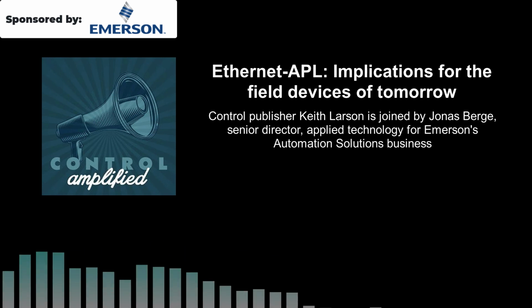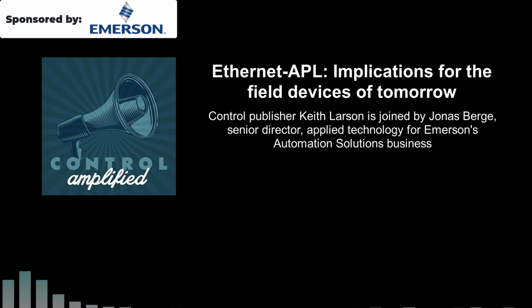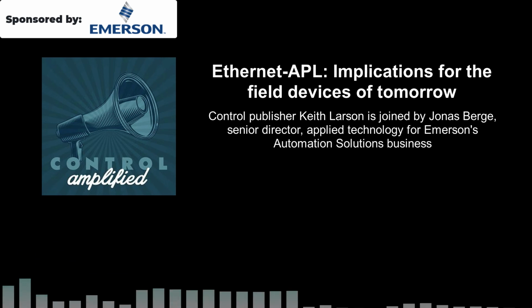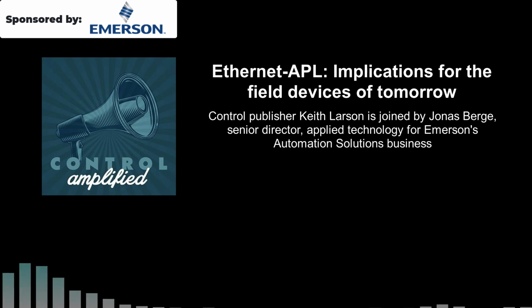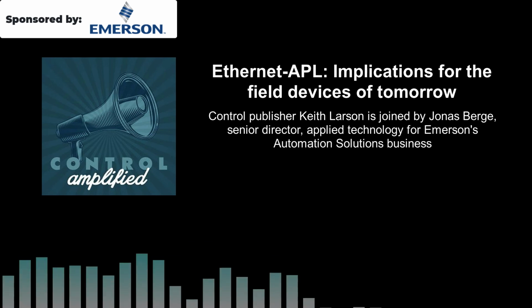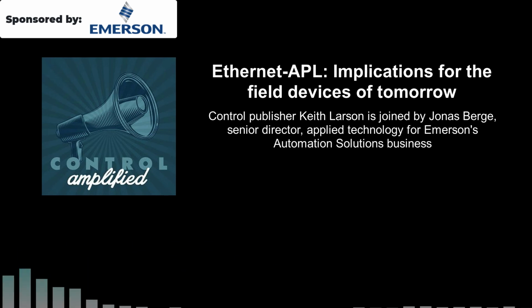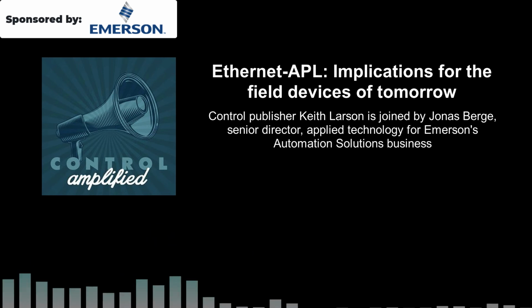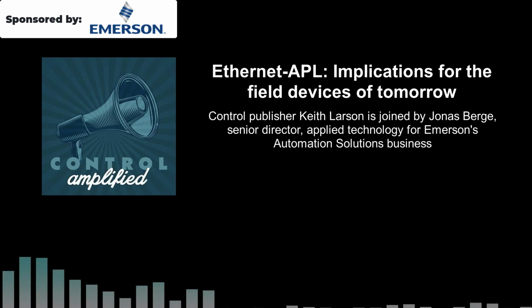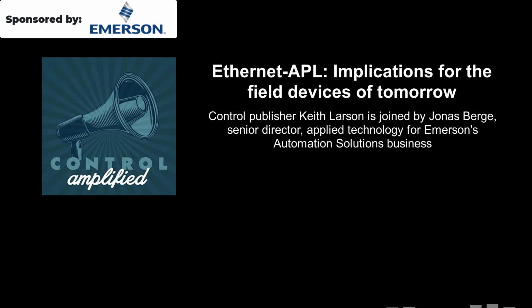Make sure to use the right application protocols for the right application. That could mean your motor controls might be using Profinet, Modbus TCP, or OPC UA, while your instrumentation uses HART-IP. With a modern DCS, that's not going to be a problem at all, because they support all of these protocols. So no issue.